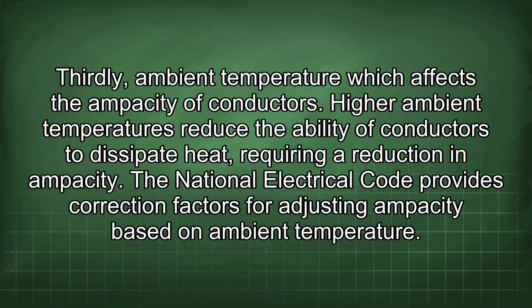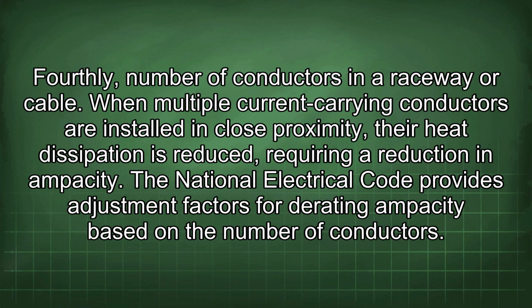Thirdly, ambient temperature, which affects the ampacity of conductors. Higher ambient temperatures reduce the ability of conductors to dissipate heat, requiring a reduction in ampacity. The National Electrical Code provides correction factors for adjusting ampacity based on ambient temperature. Fourthly, number of conductors in a raceway or cable. When multiple current-carrying conductors are installed in close proximity, the heat dissipation is reduced, requiring a reduction in ampacity. The National Electrical Code provides adjustment factors for derating ampacity based on the number of conductors.